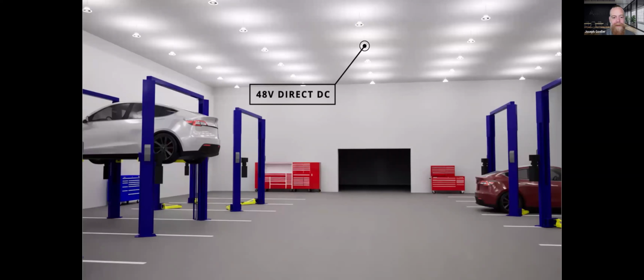So we swapped all that out with 250-watt LED high bay fixtures, each delivering 50,000 lumens. But instead of powering them with AC like most retrofits, these run natively on 48-volt DC coming from the microgrid. That eliminates fixture-level AC to DC conversion losses and thermal stress, so we're not generating heat at each fixture, and we're using a much higher quality DC power feeding these LEDs. You end up with higher reliability and longer lifespan. All of these lights at 250 watts add up to 10.5 kilowatts, completely removed from the AC grid.